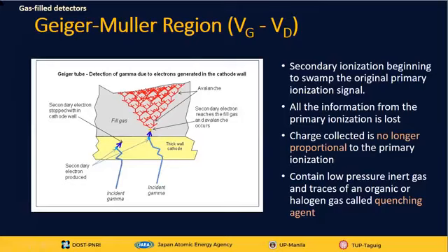And due to the extensive reaction in Geiger-Müller tubes, they experience high dead time rates, meaning that there is a lag between the pulse cascade and when the gas is able to revert to its original state so they can be ready to detect another pulse.